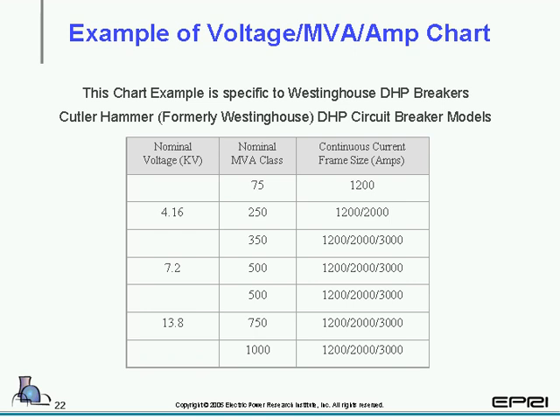Here we have a little chart of an example of what may come from the manufacturer. This one is a Westinghouse DHP breaker, and it tells the nominal voltage that the equipment can be used at. It shows the MVA class and the continuous current frame size.